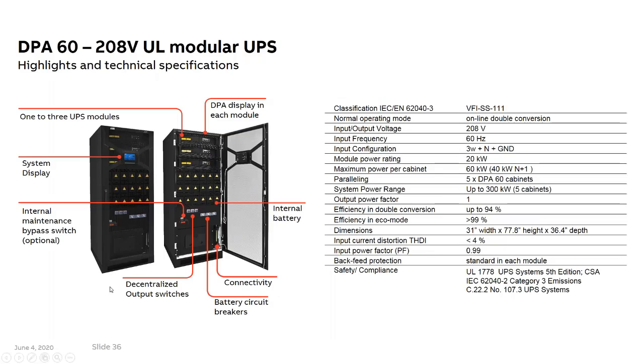And finally, I call the DPA 120 the little brother. I guess this is then the baby brother. It's based on the same power module, the 20 kW, but only has space for three of them. So 3 times 20 kW makes up to 60, and then the remaining space is utilized for built-in batteries. So if a customer doesn't need more than 60 kVA or 40 kW N+1, this is a solution. All the other UPSs we talked about need external battery cabinets for the energy storage. This one has space to have it built in. So for small data centers up to 60 kVA, or data closets of 40 kW N+1, this saves space and it's clearly the optimum solution.